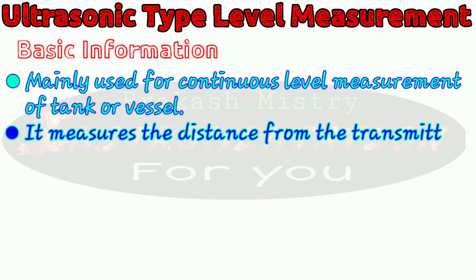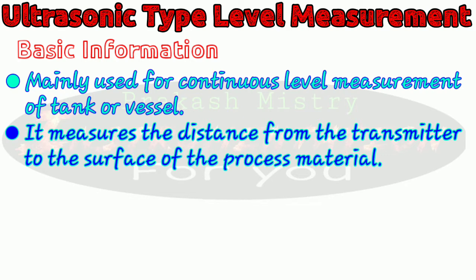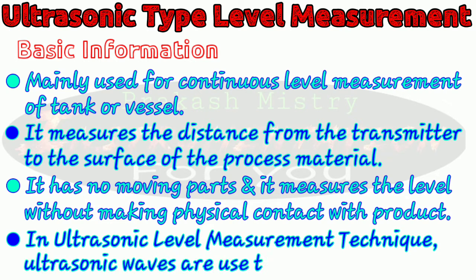An ultrasonic type level measurement system is mainly used for continuous level measurement of a tank or vessel. An ultrasonic level measuring instrument measures the distance from the transmitter to the surface of the process material. The ultrasonic level transmitter has no moving parts and it measures the level without making physical contact with the product. Due to this characteristic, it is more suitable for measuring the level of tanks containing corrosive, boiling or hazardous chemicals. Similarly to radar type level measurement which uses radio waves, ultrasonic level measurement uses ultrasonic waves to find out the level of the product in the tank, silo or vessel.